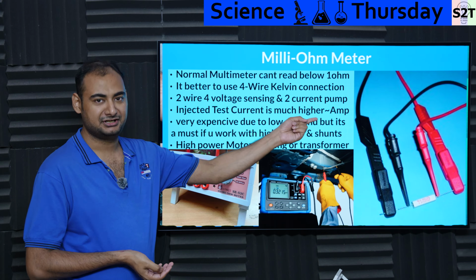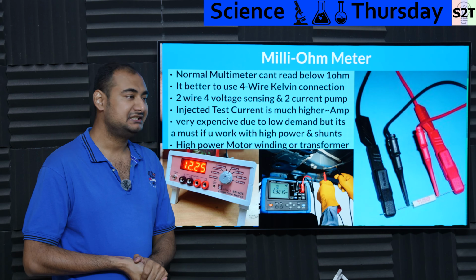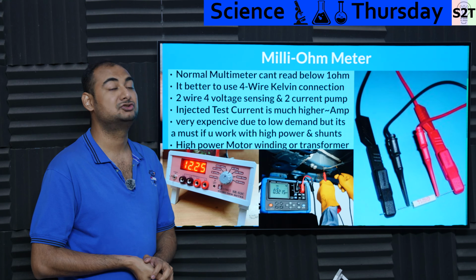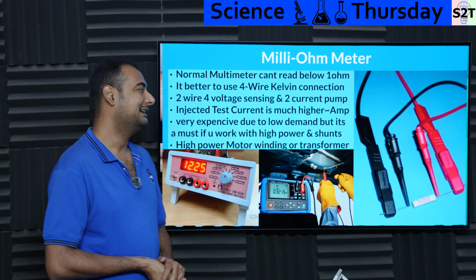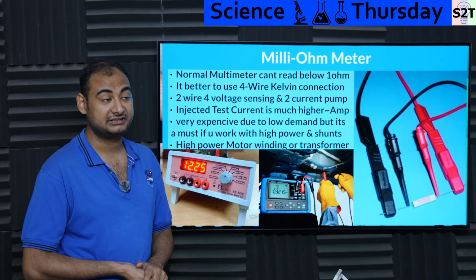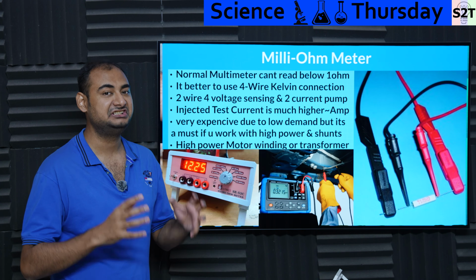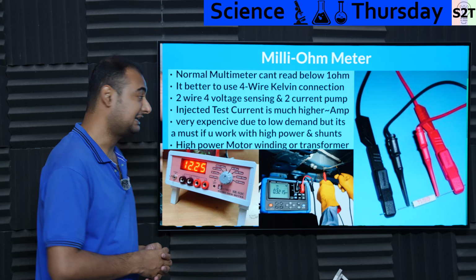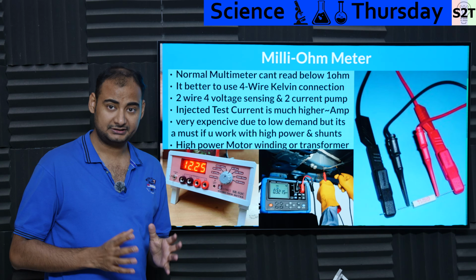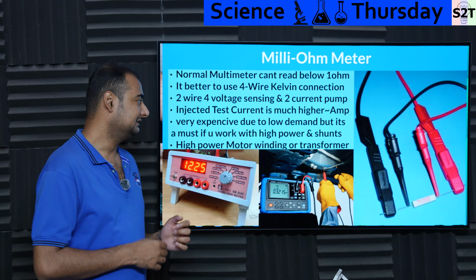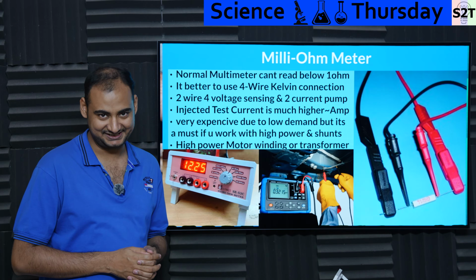You amp it up, as in you can easily start with 100 milliamps, which is exponentially larger than most meters, and go into a few amps or even tens of amps, serious amounts of current. That has to be done. However, because of low demand, these things are bonkers expensive.